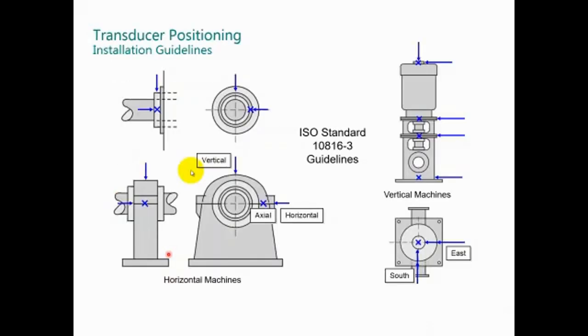The installation guidelines. For any case-mounted transducer, there's the positioning, the mounting, the adapters, boots, housing, and power signal. The transducer position depends on the ISO 10816-3 standard - how to install case-mounted transducers in different machines. This is the recommendation from vertical machines, from horizontal machines. This is true vertical, true horizontal, and axial. For vertical machines, you need to install X, Y, and axial. Please refer to the ISO standard before selecting the installation.